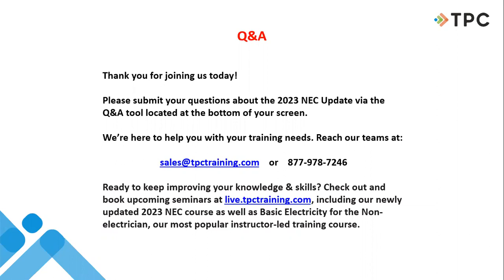Regardless, anytime I do a code class anymore, I get questions along those lines. I can't believe they want a refrigerator on a ground fault device. I can't believe they want a sump pump on a ground fault device. They're weighing the shock risk against the inevitable inconvenience of having a nuisance trip. I'm not saying that you're not going to have nuisance trips. I think we're always going to have them, but I honestly believe that the frequency of nuisance trips that we see with the modern level of quality in ground fault devices isn't nearly as high as what we think.